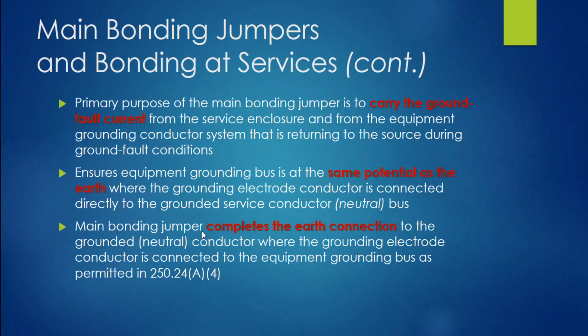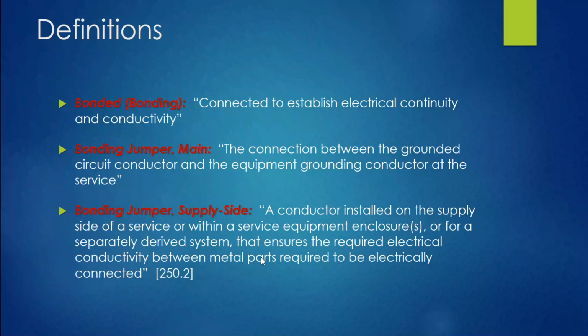All right, next, the main bonding jumper completes the earth connection to the grounded neutral conductor, where the grounding electrode conductor is connected to the equipment grounding bus as permitted in 250.24(A). And I will show you an example of that in a later slide.